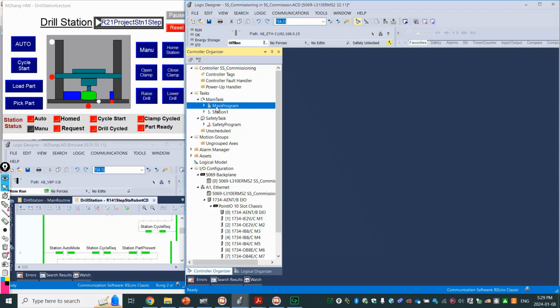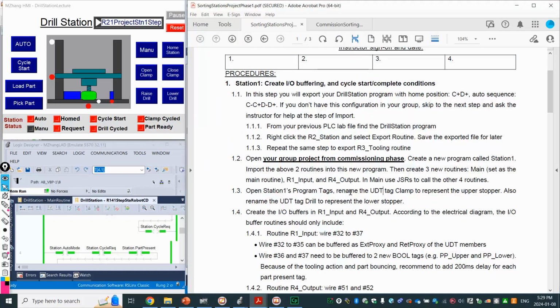You don't want this part of the program to run again, so you don't have to delete it—you just need to drag and drop it into the folder called unscheduled. Once you drop it, that will be blocked from running. You don't want what you programmed during commissioning, remember, by that time we were just doing a temporary test. That's what commissioning means—we just need to briefly, temporarily test the functions. Now we want to formally program the station.